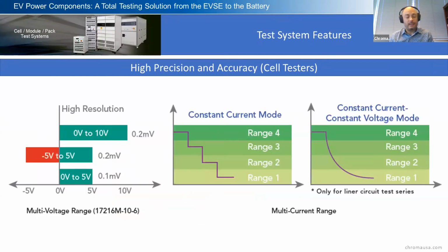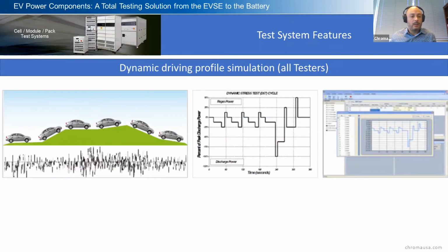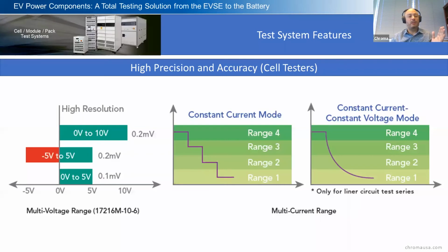For our cell testers, it's important to highlight that we have multiple voltage ranges, 3 in total. We can go from 0 to 10 volts, or -5 to 5, or 0 to 5 volts, and you can see the accuracy on each one. We also have different constant current modes and ranges for CC and CV mode, so you can accurately program down into the microamps with the accuracy and precision of our instruments.